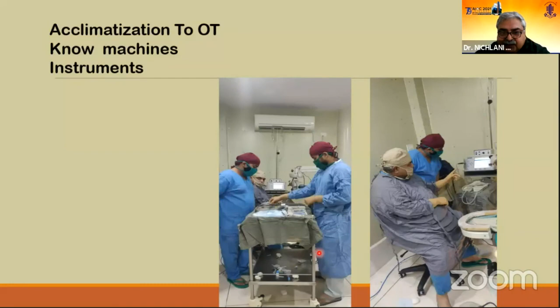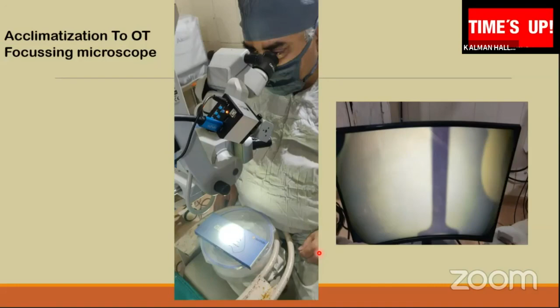This is a very important step: before operating, you must focus your operating microscope, because if a variety of surgeons are focusing the operating microscope, then definitely there will be a change while you're operating any case. So before you operate, try to see that the focus of the microscope is perfect or not. Change the eyepiece setting according to your need, and later on you can definitely mark those settings with your own calibration.